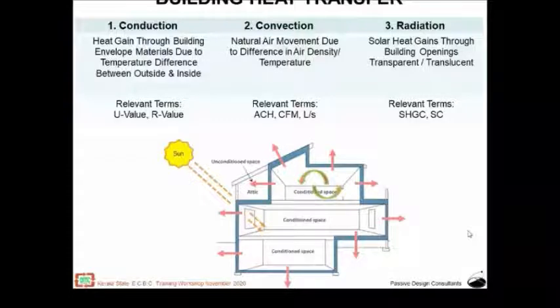At the same time, when we are bringing in outside air, we are also exhausting the cold air or the conditioned air, which is of poor air quality. So that poor quality air, which is yet conditioned, if thrown out, should be dealt with in order to retrieve its cooled character. This can be done by different air conditioning measures, different equipment like recovery wheels, etc. There is another component of convection heat gain into a building, which is called infiltration. Infiltration is when we have building openings or cracks or gaps between different materials in the envelope.